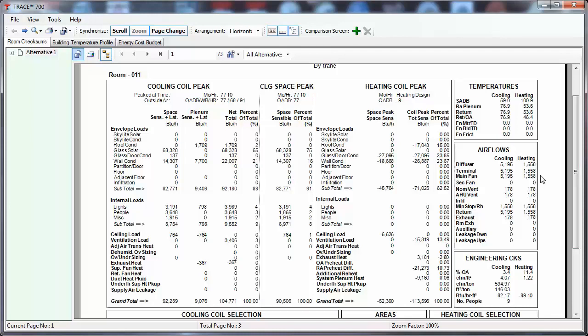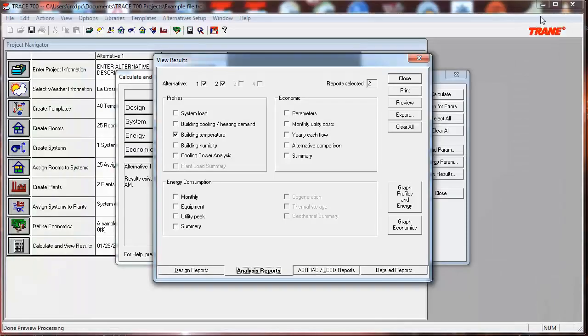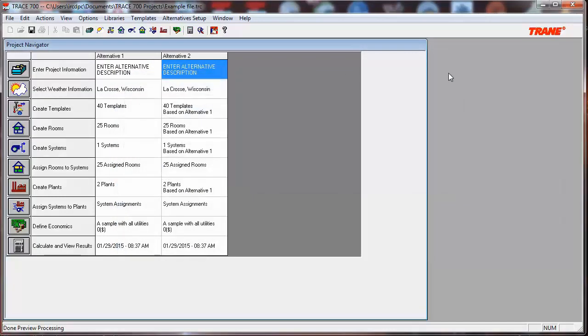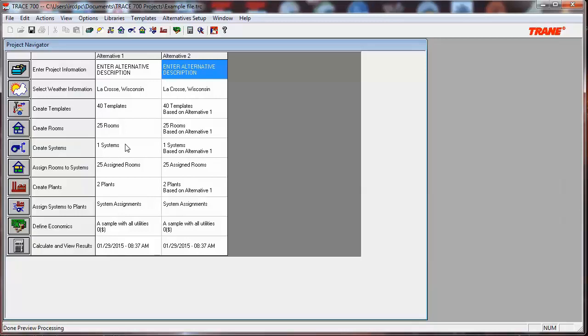A good example of this would be storage rooms or closets. This is why we suggest tip number one, which can reduce the amount of unmet load hours by combining smaller areas into thermal zones. To continue on, in CDS we have seen some room outputs with a heating supply air dry bulb matching the specified room set point because of low heating loads. So, if the set point is 72 and the room is allowed to drift to 65, then with a Supply Air Dry Bulb of 72, it will be impossible for the room to be brought back under control. Similarly, if the room is a restroom or a corridor, the outputs could read an air flow rate as small as 15 CFM for the entire space, or smaller. And as before, if the room goes into drift, then there is no way the room could ever be brought back under control with such a low air flow rate.